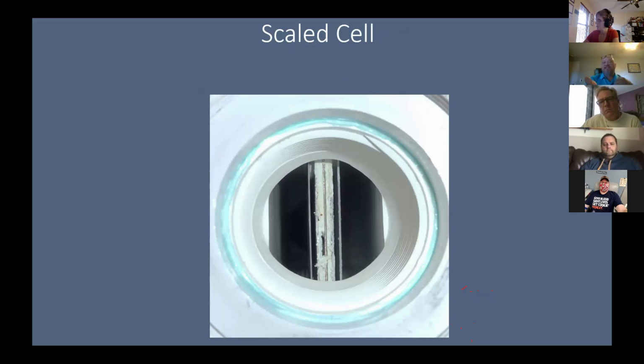All right. So if you clean this cell off, you don't want to see any kind of scale between the blades itself. You can put it back into service. If it scales up again within 2 weeks, now you know your power supply has issues with the reverse polarity, the self-cleaning feature. If it scales up longer than 2 weeks, then you know you've got to adjust your water chemistry to balance water conditions.